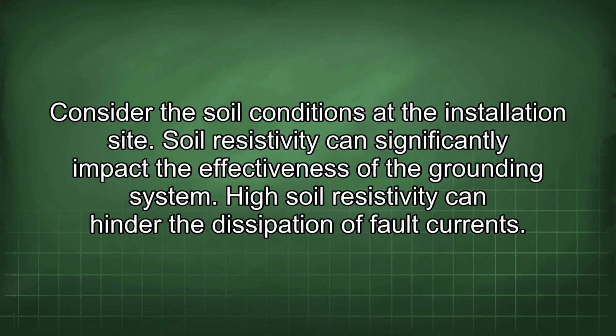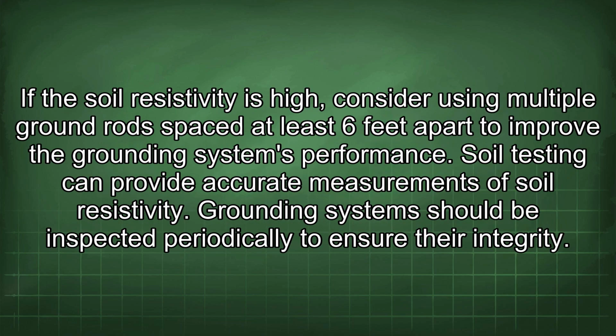Consider the soil conditions at the installation site. Soil resistivity can significantly impact the effectiveness of the grounding system. High soil resistivity can hinder the dissipation of fault currents. If the soil resistivity is high, consider using multiple ground rods spaced at least 6 feet apart to improve the grounding system's performance. Soil testing can provide accurate measurements of soil resistivity.